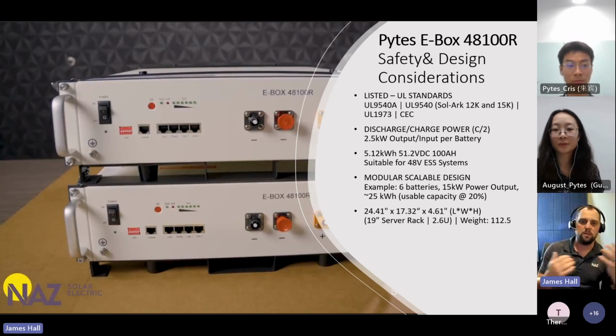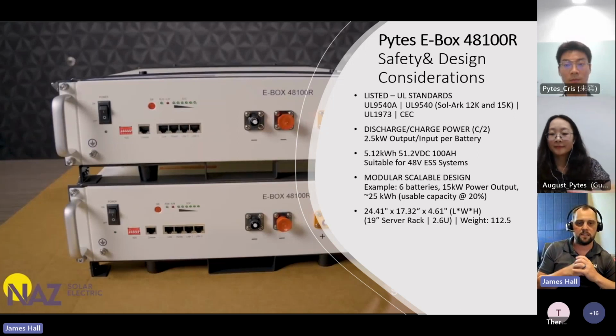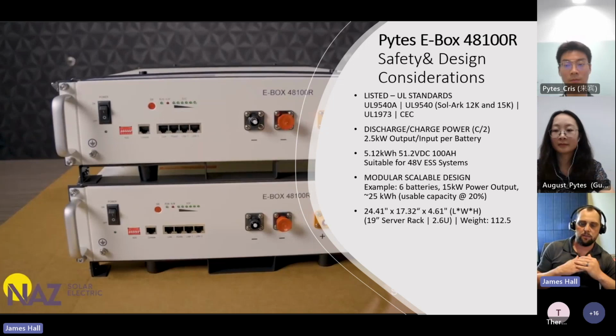If you're trying to put this on a 10 kilowatt inverter, ideally you want 4 batteries so you can get that continuous 10 kilowatt output into the inverter. That's the hypothetical consideration - we'll cover in a minute how to wire that. This is a 5.1 kilowatt hour battery, very modular and scalable. You can put 6 batteries, for example, on everyone's favorite inverter, the Sol-Ark 15K, and that gives you, give or take, about 25 kilowatt hours usable capacity, maybe a little more. We typically design around an 80% depth of discharge, but it is within warranty for Pytes to do 90% depth of discharge.